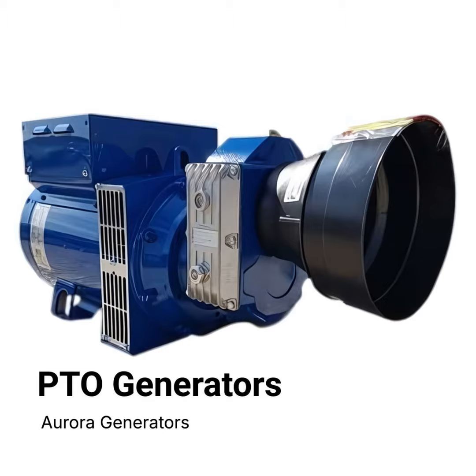Non-negotiable. Safety first, always. Following the manufacturer's guidelines, like those from Mecc Alte, during installation, operation, and maintenance is critical. And grounding, I assume that's essential. Absolutely fundamental. The generator frame must be properly grounded to prevent electric shock hazards. Who's responsible for adding things like circuit breakers? That falls on the installer. They need to ensure the whole setup includes necessary safety protections: circuit breakers for overcurrent, maybe specific overload protection, emergency stop buttons readily accessible, all the required guards and interlocks.